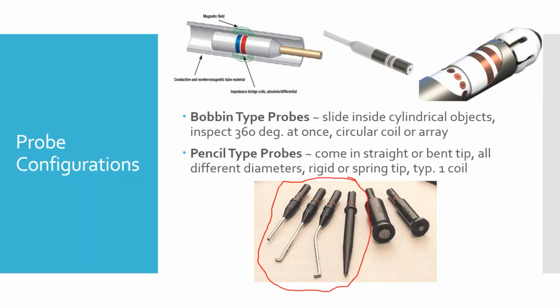Then there's the pencil probe with more of a plastic kind of grip on it, and the two spring-loaded probes you saw earlier. Again, those are all fairly small coils. So they're designed mainly for the kind of inspection where you'd go around rivets or other things to look for surface cracks in sheet metal or thinner materials.